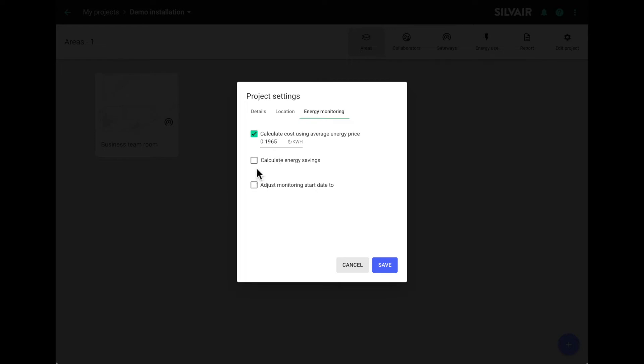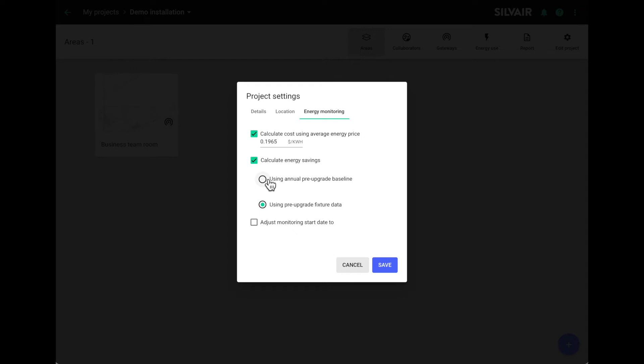Then calculate how you want to calculate the savings. We have two options. You can either choose a straightforward method based on the overall annual energy consumption for the whole building before the retrofit. We'll divide the annual value by 12 to get the average and compare it to the monitored monthly energy use of the new installation. The second method is based on comparing the energy use of the pre and post upgrade fixtures. This approach is useful if you're doing a partial retrofit and if it's a one to one replacement. Let's choose the second method so you can see how it works in practice.